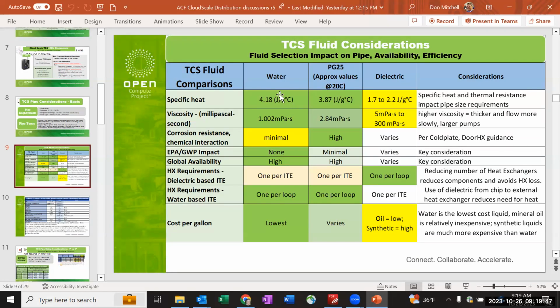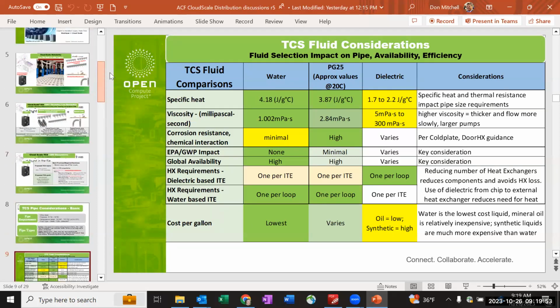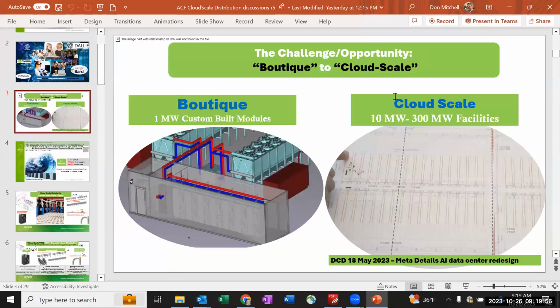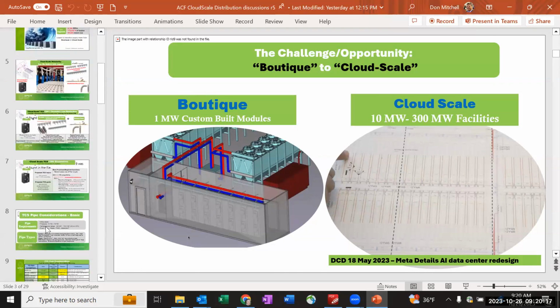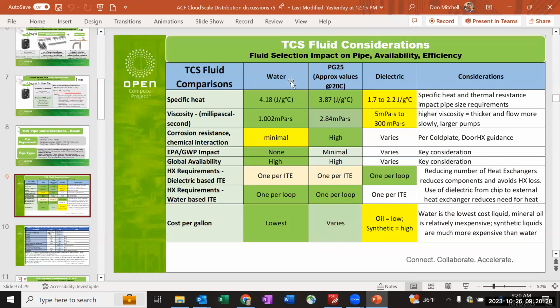So what I'm seeing is pretty much everyone, when you start talking large scale distribution, nothing comes close to water or water-based liquids for transporting heat. If you're dealing with inside the IT rack, you might work with dielectrics and small volume distributions. But for large volume distributions, this is what we're seeing: water's specific heat is 4.18, PG25 is 3.87, and dielectrics are basically half of those numbers.